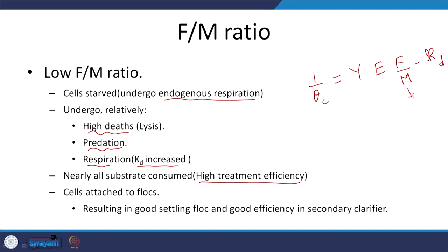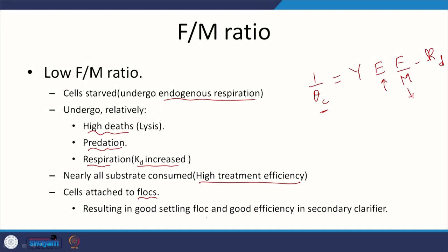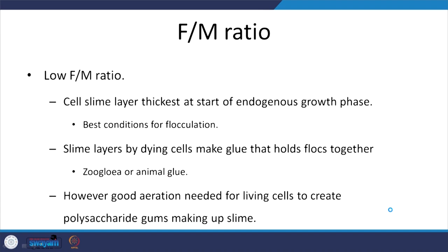With low F/M and keeping theta_c the same, efficiency increases. Also, if we maintain F/M at the sweet spot, there is going to be a slime formed and the right combination of floc-forming and filamentous microorganisms. This results in good settling floc and thus good efficiency in the secondary clarifier. The cell slime layer is thickest at the start of the endogenous growth phase, leading to best conditions for flocculation.